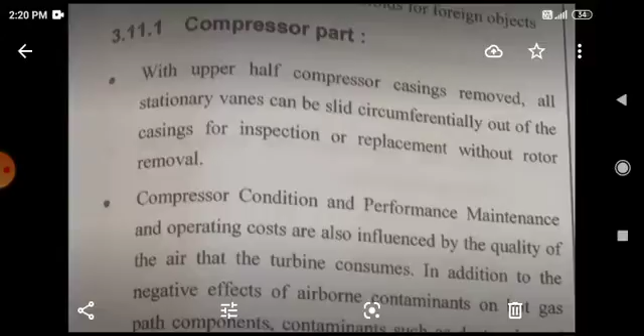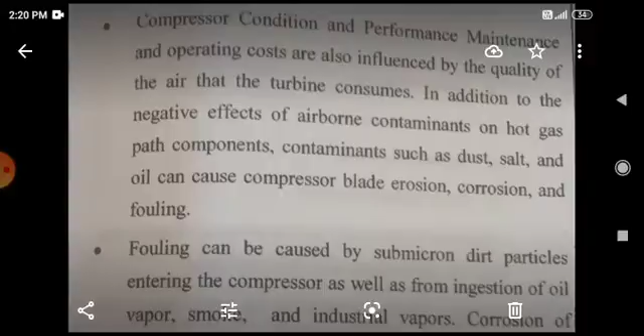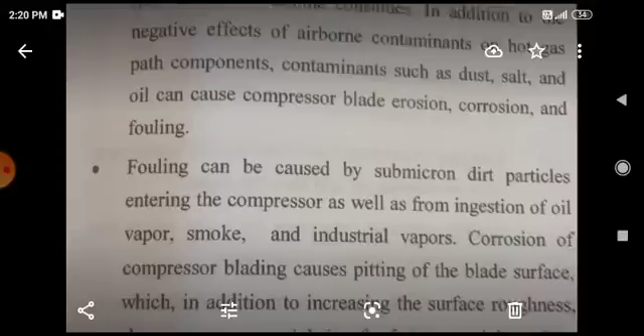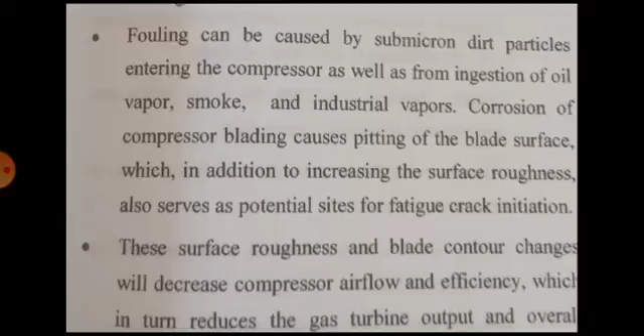that the turbine consumes. In addition to the negative effect of airborne contaminants on hot gas path components, contaminants such as dust, salt, and oil can cause compressor blade erosion, corrosion, and fouling. Fouling can be caused by submicron dirt particles entering the compressor as well as from ingestion of oil, vapor, smoke, and industrial vapors. Corrosion of compressor blading causes pitting of the blade surface, which in addition to increasing the surface roughness also serves as a potential site for fatigue crack initiation.